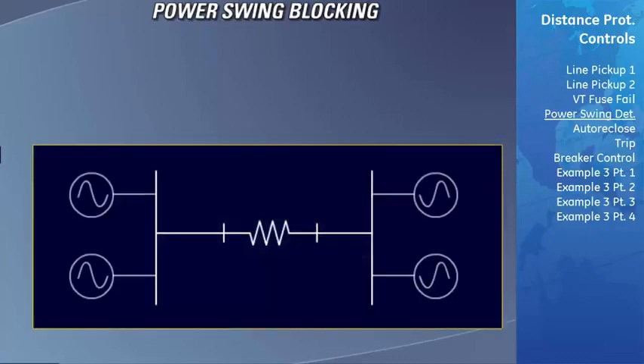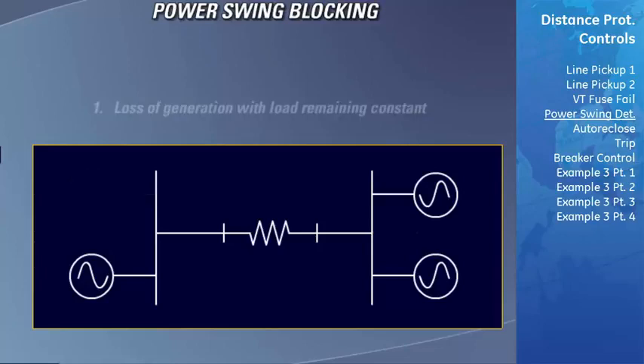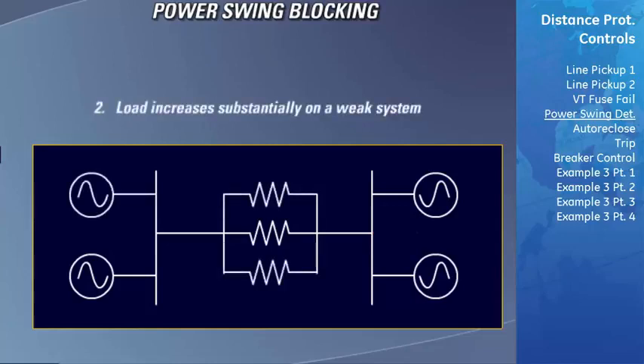A stable power swing is a condition where a system loses synchronism for a short period of time with a neighboring system and then later regains synchronism. There are 2 reasons that a power swing such as this can occur. The first scenario is one of the systems loses a significant amount of generation, therefore instantly becomes much weaker, and the load of the system remains constant. The second is the system being already weak and the load suddenly increasing substantially.